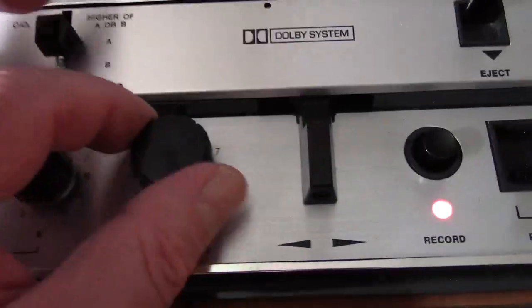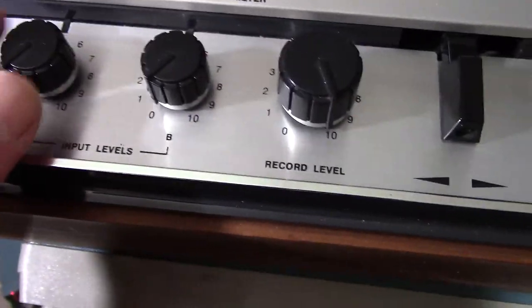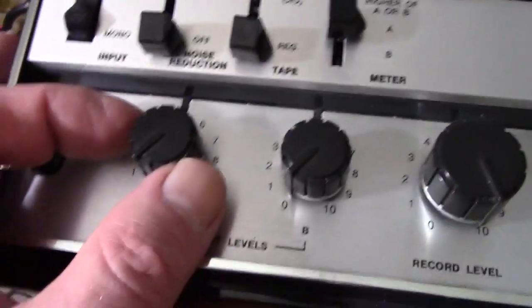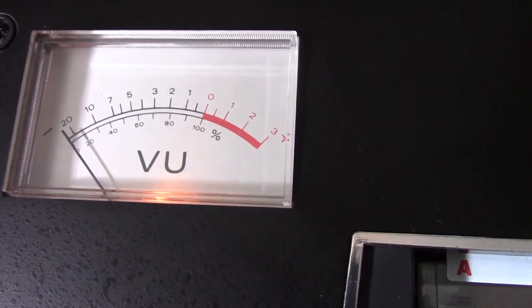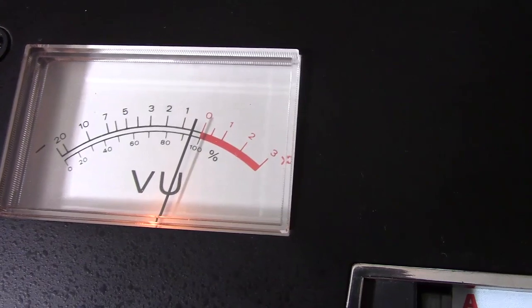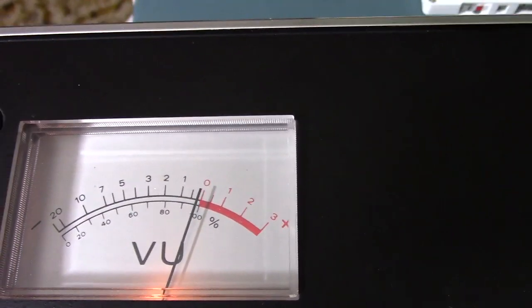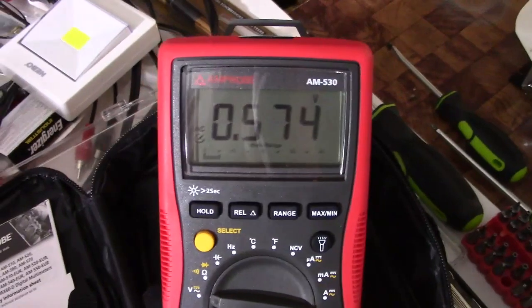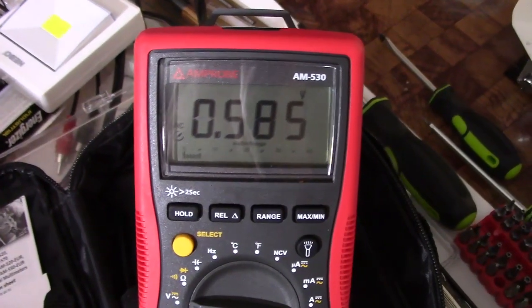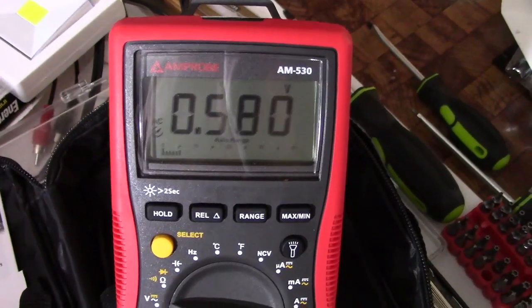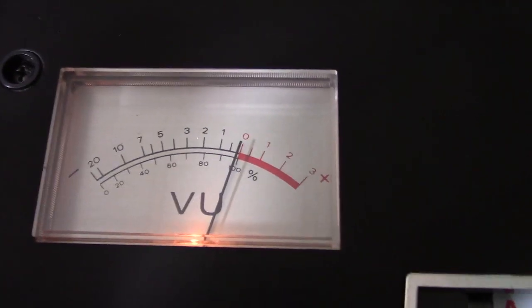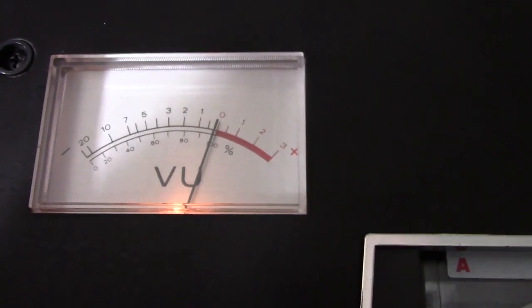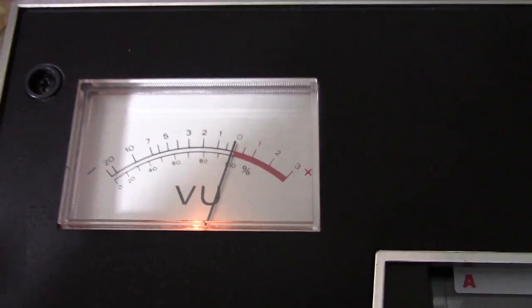So what it says to do is turn your volumes all the way up, on this one all the way up, and then go to channel A, and turn channel A's knob until you get a 0 reading on this meter here. Try to get the parallax error out of there, and it should be 0.58. You can see right there, if I tweak it to 0.58, as close as I can get it, the meter is 0, and that is a good calibration point. That is what's called meter sensitivity, and that's all taken care of.